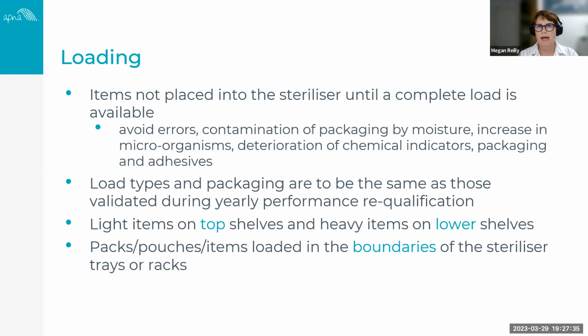So the load types and the packaging need to be the same as those that your external service provider has validated during your yearly performance requalification. If you change the loads, and as I said before, if you change your packaging, you need to go through that validation process. You need to be assured that those items and that packaging is being reprocessed to the correct level. So I've just put a few little tips: light items are placed on top shelves, heavy items tend to go on the lower shelves, and packs or pouches or other items are loaded well within the boundaries of the steriliser tray or the racks.